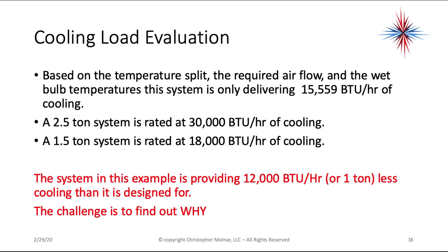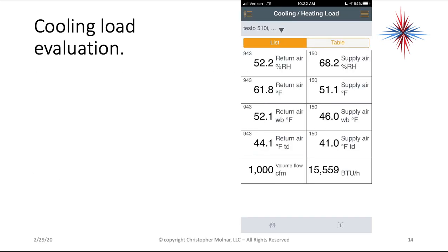There's a lot of extra money being wasted on this system because it's not providing the cooling it's supposed to be providing. So again, we can get that from using the proper tools and using the proper readings. Now, granted, what I have here is giving us more information faster, but you can do the same things by using a chart.